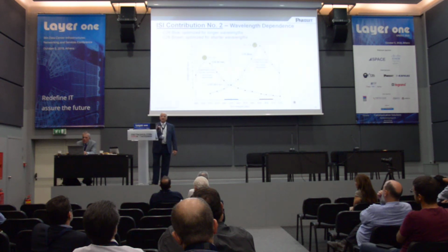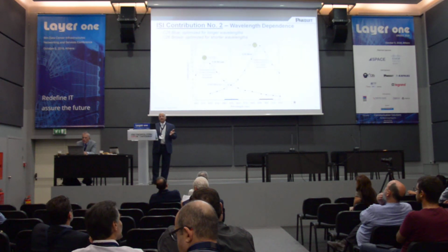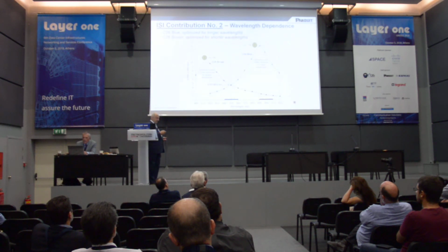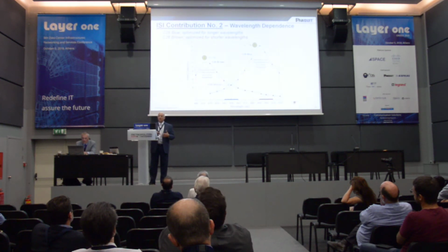The other thing about how it affects intersymbol interference is that transceivers are specified to have a wavelength of 850 nanometers. Unfortunately, very few of them have 850 nanometers. They can vary plus or minus 10 nanometers. So the bandwidth is measured at 850, but you now put it into the field with a VCSEL that is, say, 845 nanometers, and depending on which fiber you have, you could have a very big difference in actual modal bandwidth, modal dispersion. So it impacts your intersymbol interference again.